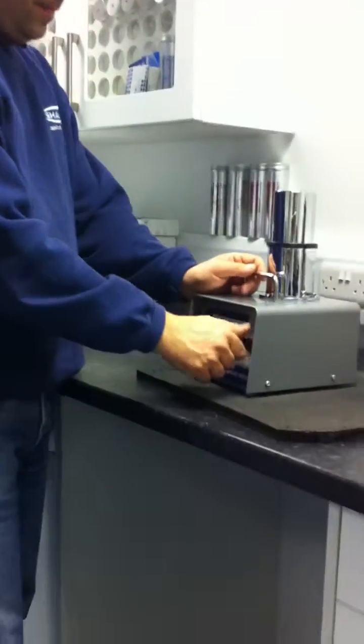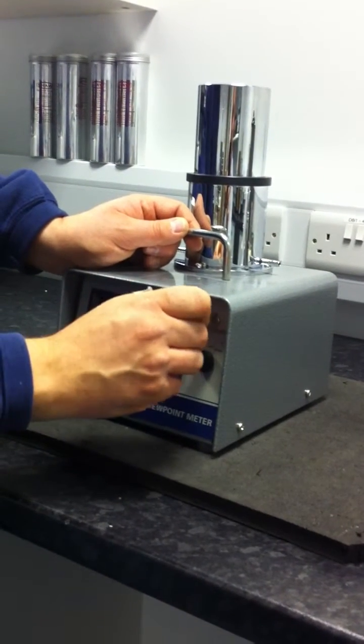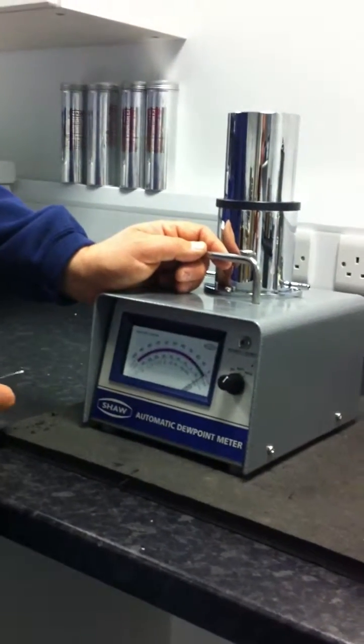Switch the meter on and auto-cal the sensor to the meter to take it to your zero — the end of the scale — depending on which instrument you're on.